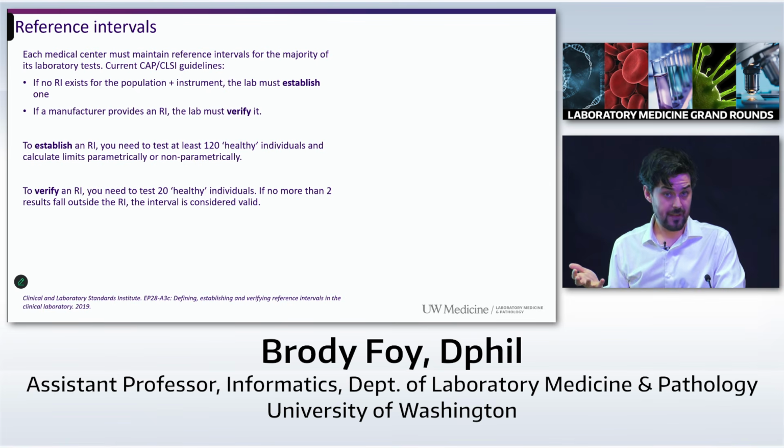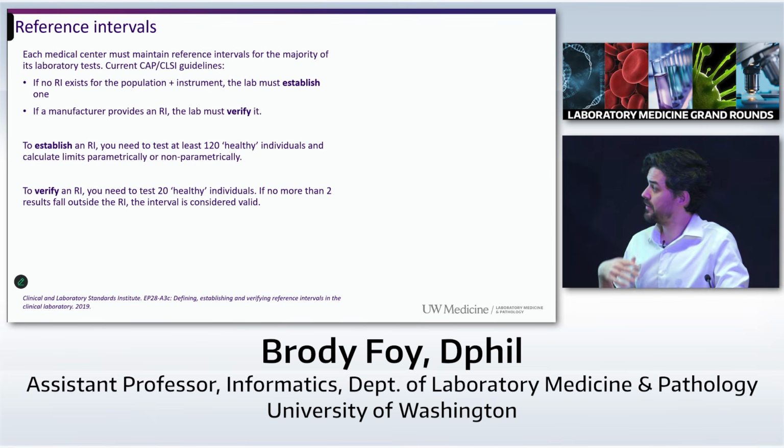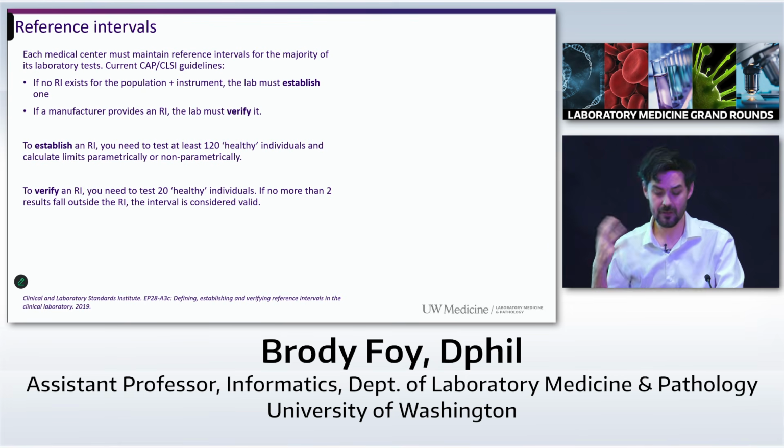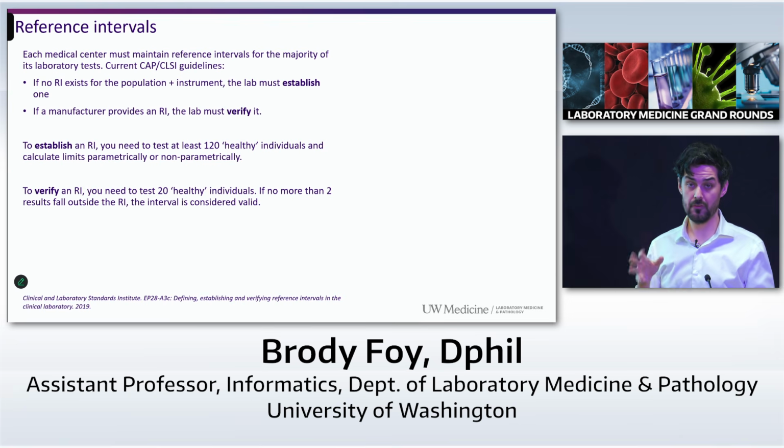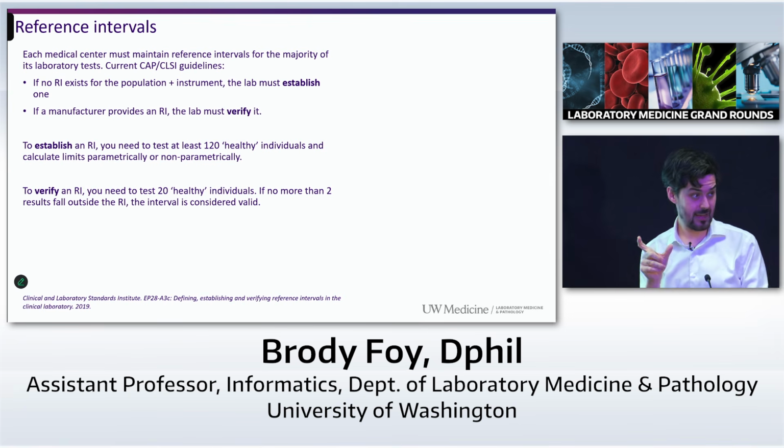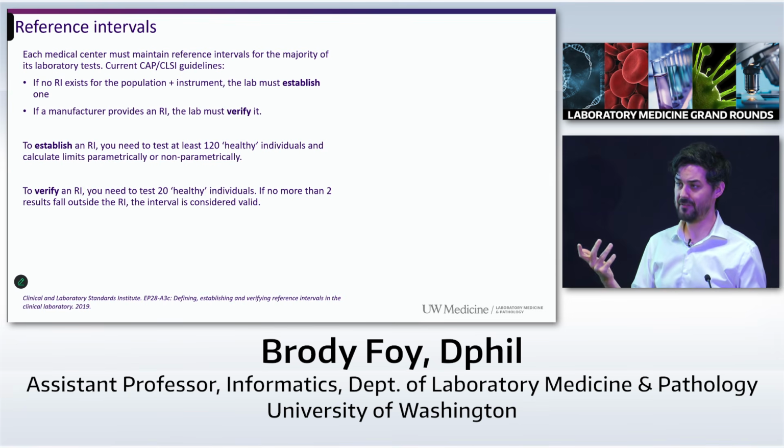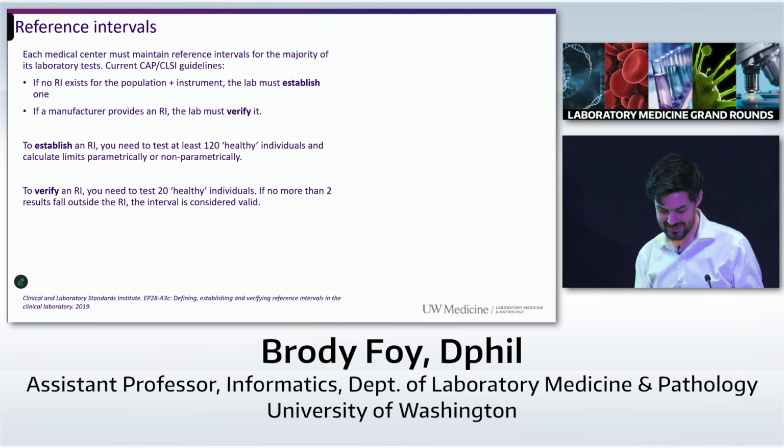And if you only want to verify, it's a lower standard of evidence, so they say you only need 20 individuals, and if no more than 2 of the 20 results fall outside that reference interval, it's considered verified and fit for use.